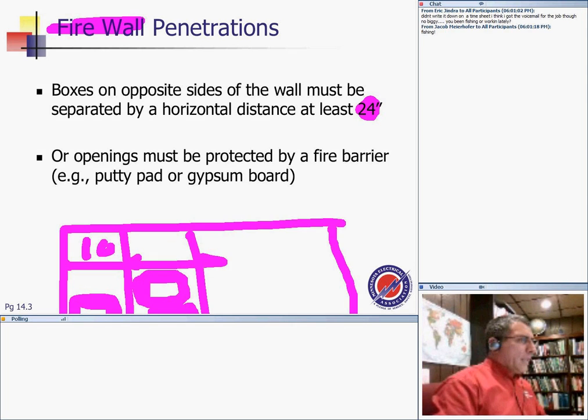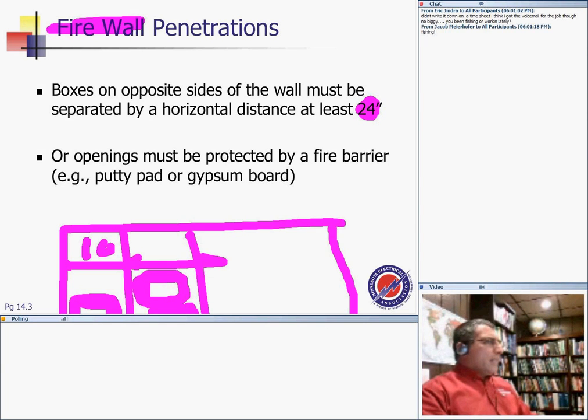Again, we're only talking about a fire-rated wall. A fire-rated wall in a dwelling, my friend, is the wall between an attached garage and the house. That would be a fire-rated wall. Double sheetrock. Use a special type of non-metallic box. You have to use fire-rated boxes in it, and to maintain it, you don't put them in the same cavity and so forth. Any question about that?